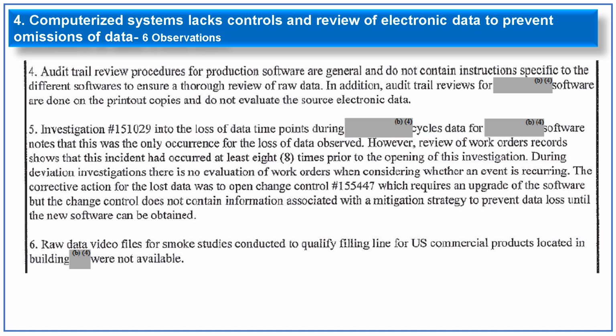The fifth observation: the investigation into a loss of data point in the software notes that this was the only occurrence of the loss of data. However, review of the work orders shows the incident has occurred 8 times prior to the opening of this investigation. So during this deviation investigation, there was no evaluation of the work orders to consider whether this event was recurring. The corrective action for the loss of data was to open a change control for an upgrade of the software, but the change control does not contain information associated with the mitigation strategy until the new software has been obtained.